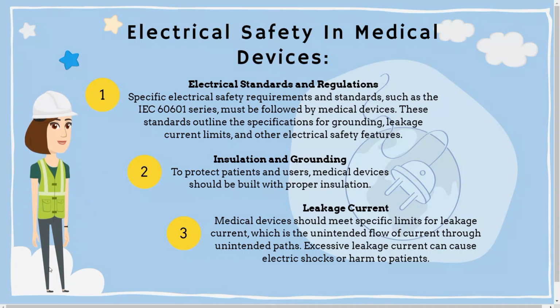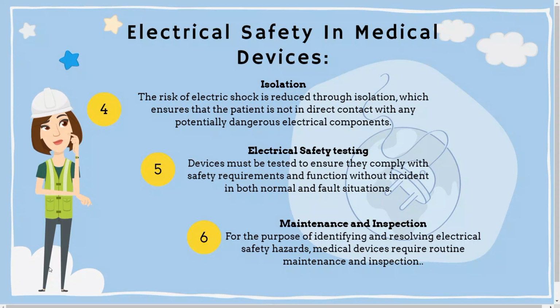Excessive leakage current can cause electric shocks or harm to patients. Fourth, isolation. The risk of electric shock is reduced through isolation, which ensures that the patient is safely not in direct contact with any potentially dangerous electrical components. Fifth, electrical safety testing.